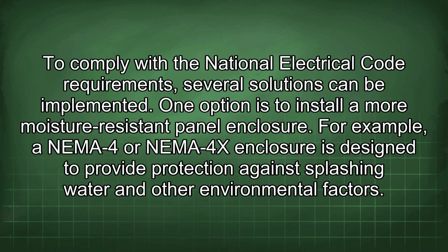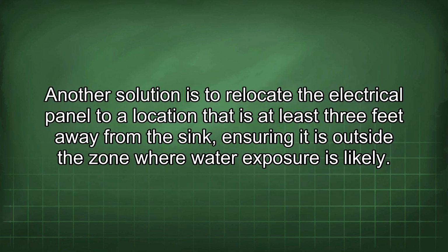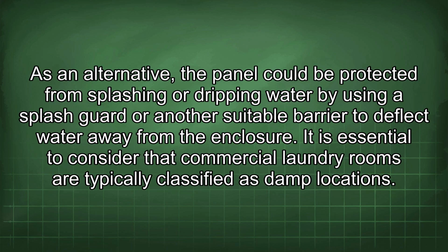To comply with the National Electrical Code requirements, several solutions can be implemented. One option is to install a more moisture-resistant panel enclosure. For example, a NEMA-4 or NEMA-4X enclosure is designed to provide protection against splashing water and other environmental factors. Another solution is to relocate the electrical panel to a location that is at least 3 feet away from the sink, ensuring it is outside the zone where water exposure is likely. As an alternative, the panel could be protected from splashing or dripping water by using a splash guard or another suitable barrier to deflect water away from the enclosure.